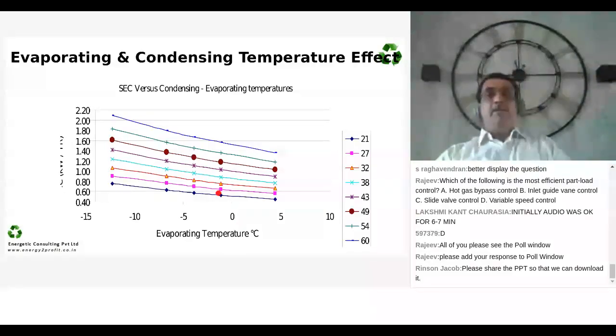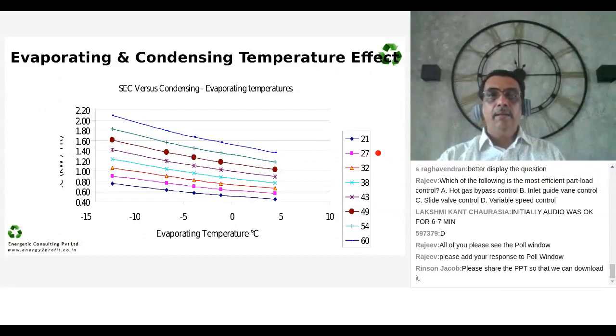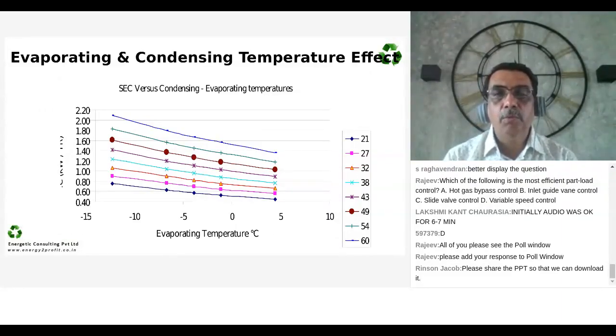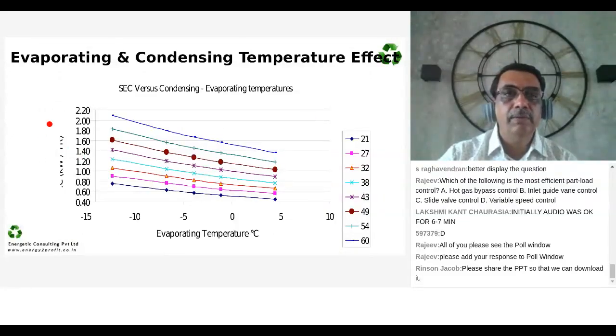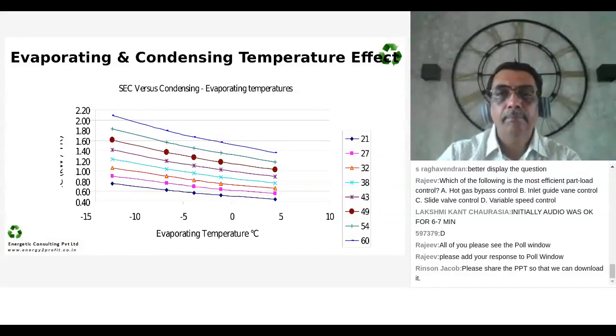Now I go to the next aspect. What is the effect of evaporating and condensing temperatures on the performance of a refrigeration system? Let's look at the evaporating temperature as it is moving from left to right, higher. You can see that the specific energy consumption is coming from higher to lower. So, in a nutshell, you can conclude this way. This is kilowatt per TR. Putting it again, this is kilowatt per TR.